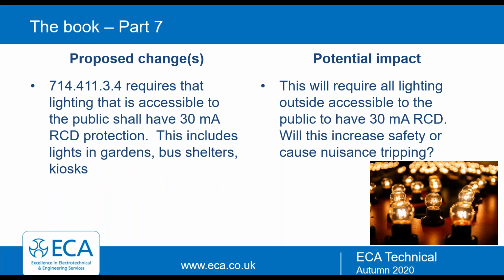Another one in part 7: outside lighting requires that any lighting accessible to the public has 30 milliamp RCD protection. So all outside lights accessible to the public - so my local pub round the corner would have to put a 30 milliamp RCD on its outside lighting, is that right? I guess it is. Would that cause a potential problem with nuisance tripping? Well, it's certainly going to increase the possibility. Excellent - well, maybe that's something to consider if you're doing those sort of things.